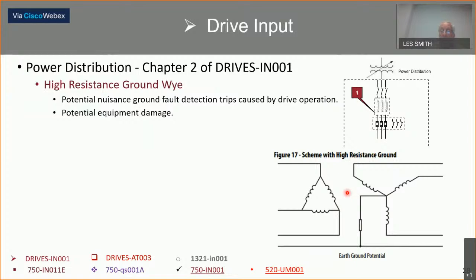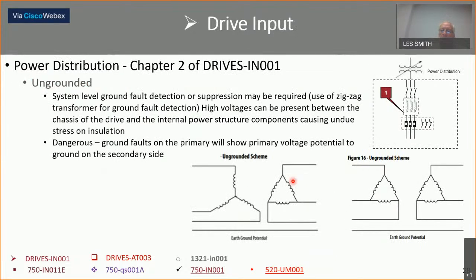And at a later point, we'll come out and find the ground because we'll have indicators out here that say we're grounded, but we continue to run. I find that still applied today right next to transformers that are grounded. I have single plants that have both systems in them. And here's a Y delta or delta delta, totally ungrounded on this. And the dangers are your ground can rise up and cause damage to your components.